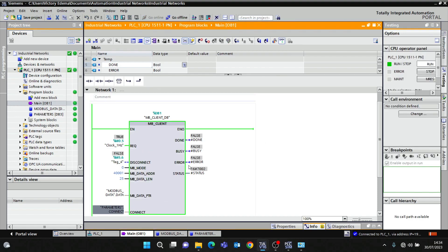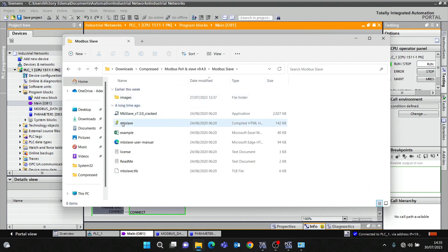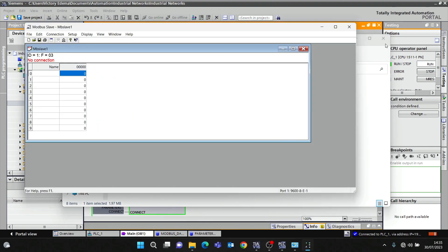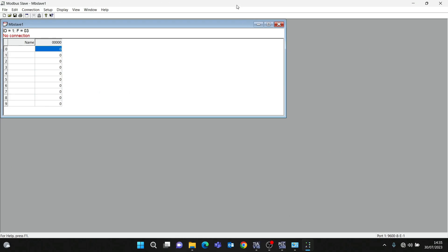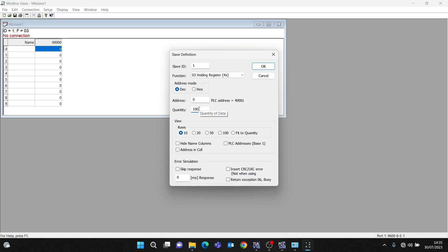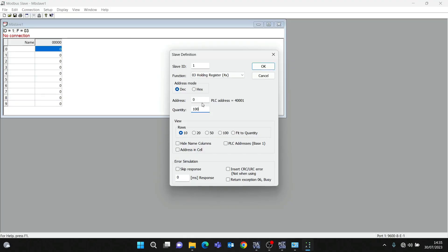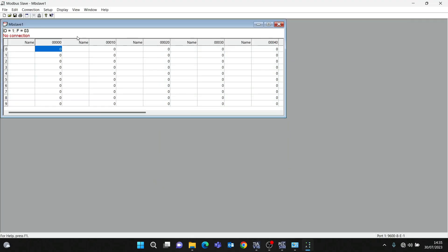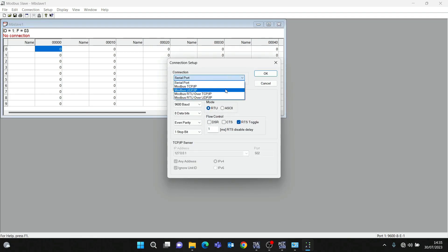Now I'll launch my Modbus server, which is Modbus slave, which is my simulator. Then I'll do the parameterization setup. I want my slave to be 0 to 100. You can see PLC address 40001. What you are reading in your client should not be more than what is contained in the master. We're reading 25 for data length integer, so I want this to be 100 holding registers.